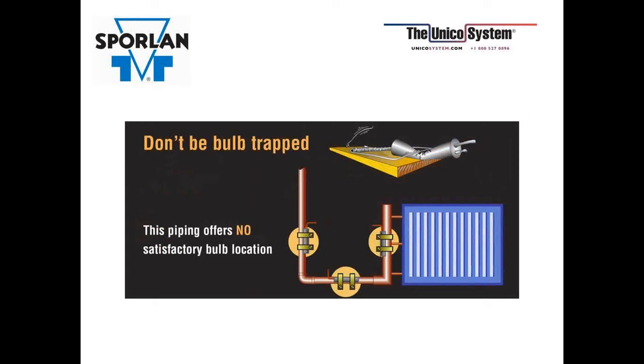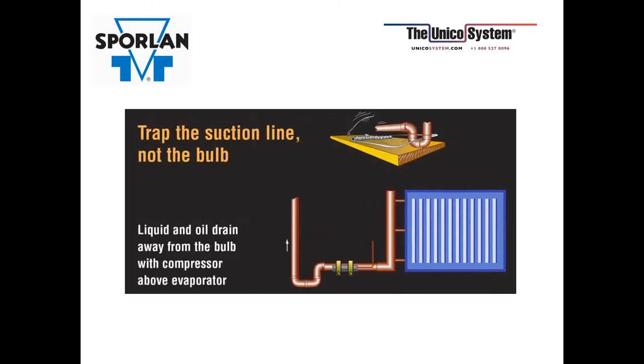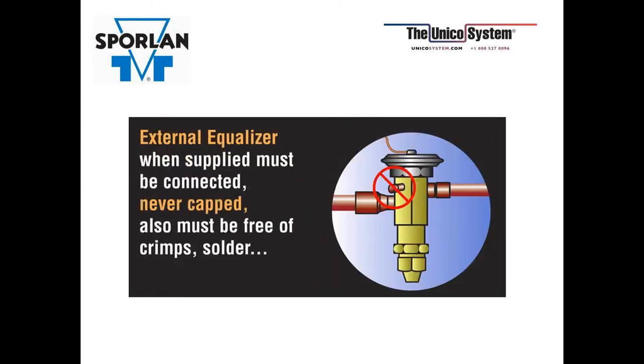a good spot. If you have to go on a vertical line, we always say horizontal, but if you have to go on a vertical line, the issue there is going to be when that oil does drop out, you don't know exactly where it's going to cling to the pipe, so you might have to find the sweet spot and just experiment with that bulb location. But in this case, you have to repipe to get this in a good spot. And here you trap the suction line, not the bulb. And this is better so the liquid and the oil can drain away from the bulb, and you get a good sense of what the temperature is in that line.